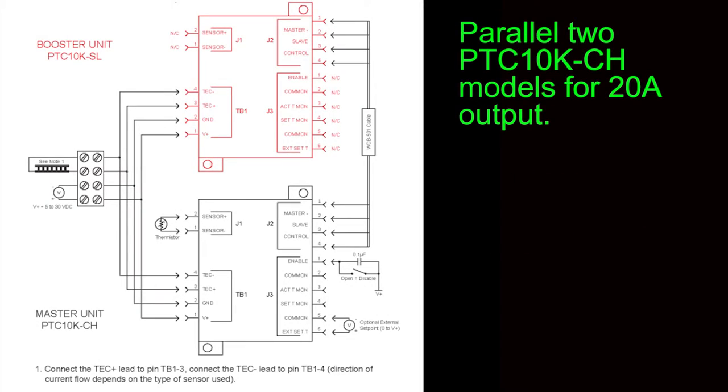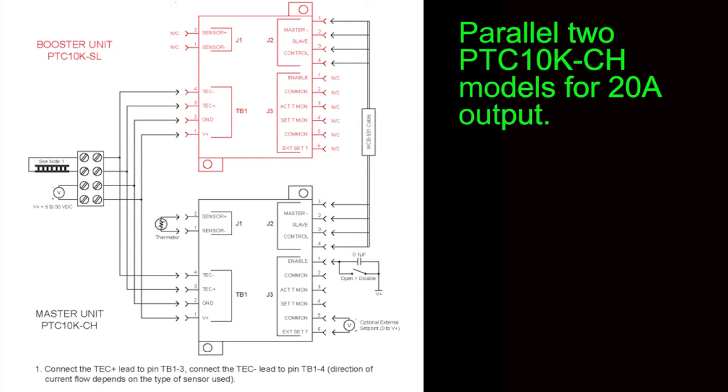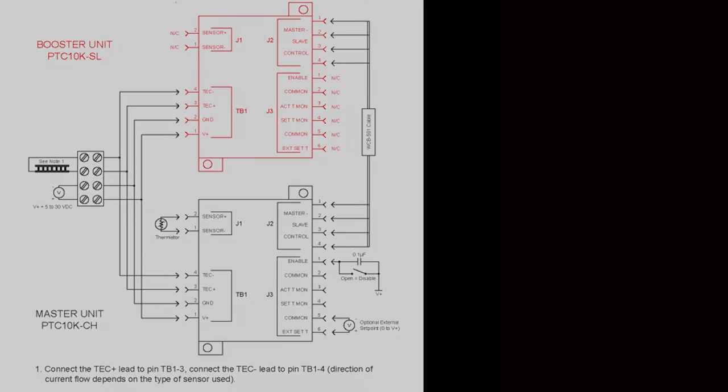The PTCs are designed to be very flexible. For example, two can be set up in master booster configuration to drive up to 20 amps. Make sure that the power supply connections are starred. This means separate power lines are run to each controller. Daisy chaining power supply inputs causes ground loops and voltage drops. This applies to all products.